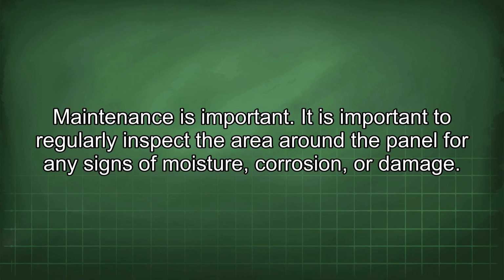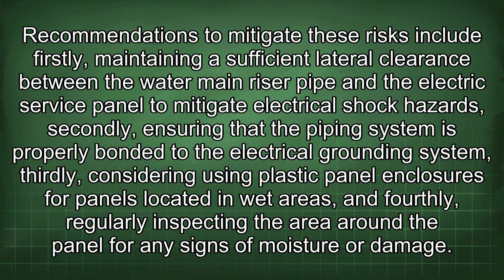It is important to regularly inspect the area around the panel for any signs of moisture, corrosion, or damage. Recommendations to mitigate these risks include: firstly, maintaining a sufficient lateral clearance between the water main riser pipe and the electric service panel to mitigate electrical shock hazards. Secondly, ensuring that the piping system is properly bonded to the electrical grounding system. Thirdly, considering using plastic panel enclosures for panels located in wet areas. And fourthly, regularly inspecting the area around the panel for any signs of moisture or damage.